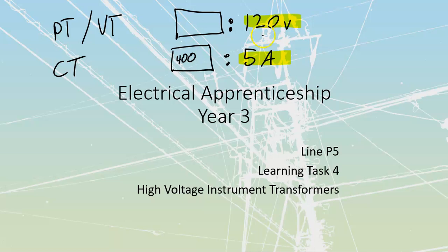Same with my PTs. If I've got a PT that is rated, we'll just put this at 1,000 volts right now because it's an easy value to work with. If it was 1,000 to 120, if we were at 1,000 volts, we would have 120 out. If we were at 500 volts, we would get 60 out, or if we were at 1,500, we would have 180 volts out. So it's always going to be scaled off of the same voltage ratios as what we have before, turns ratios, etc. But when we look at these things, we're always going to read them as being to 120 or as being to 5.